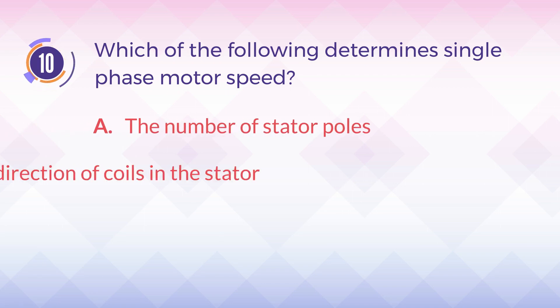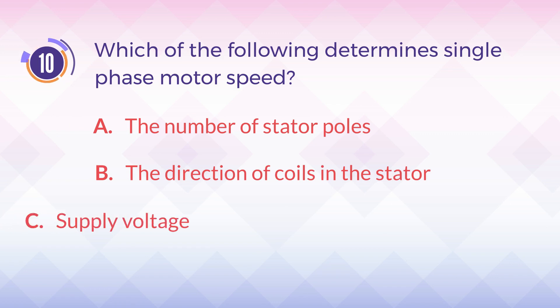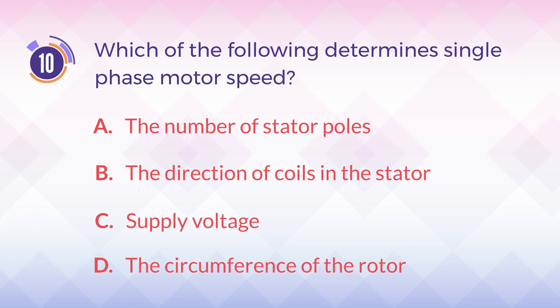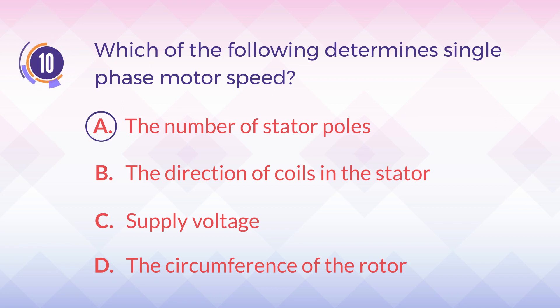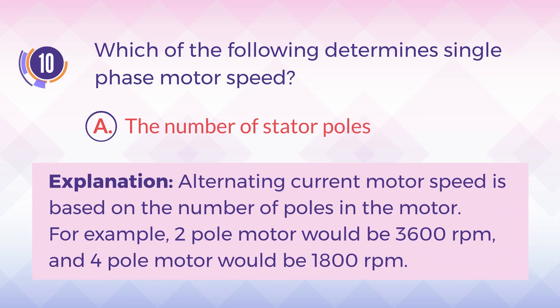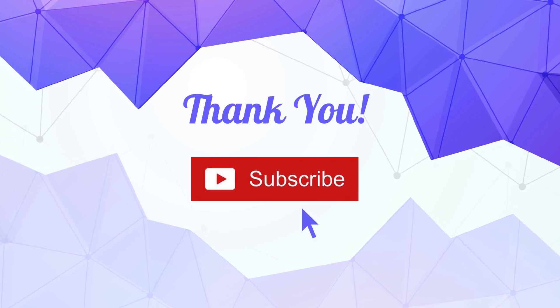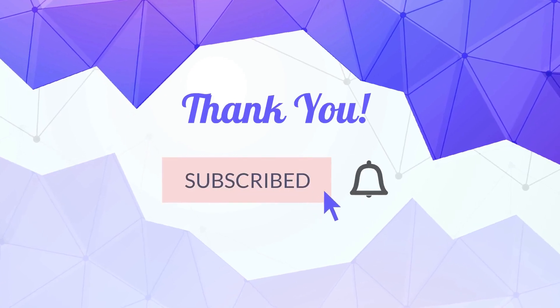Number ten: which of the following determines single phase motor speed? A) the number of stator poles, B) the direction of coils in the stator, C) supply voltage, D) the circumference of the rotor. The correct answer is A) the number of stator poles. Explanation: alternating current motor speed is based on the number of poles in the motor — for example, a two pole motor would be 3600 RPM and a four pole motor would be 1800 RPM. Thanks for watching — don't forget to like, share, and subscribe to our channel for updated videos every week.